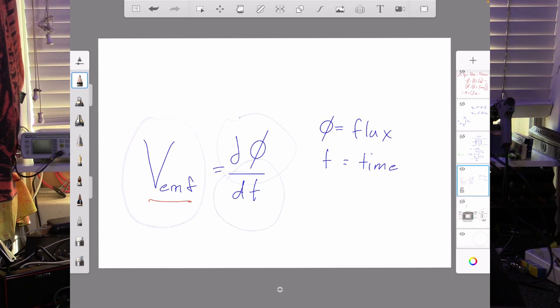When the voltage is first applied to the transformer, the flux will start to build up very quickly. The voltage will go from zero to maximum in a couple of cycles, and the current will be very large. The transformer flux may briefly saturate, and it's in this time that bad things can happen.